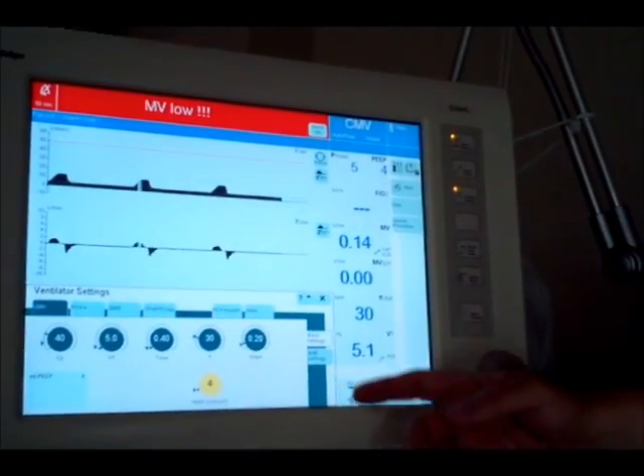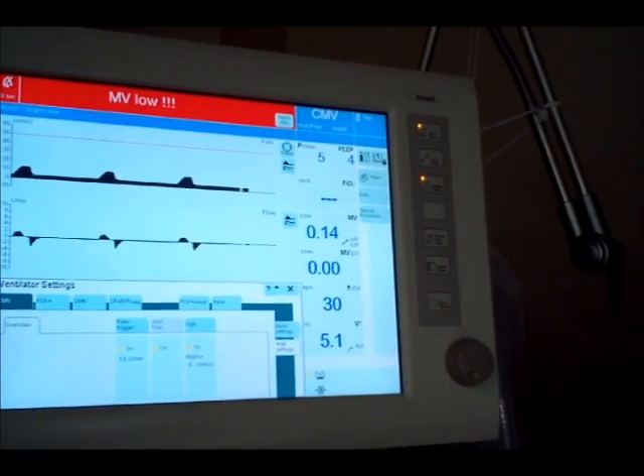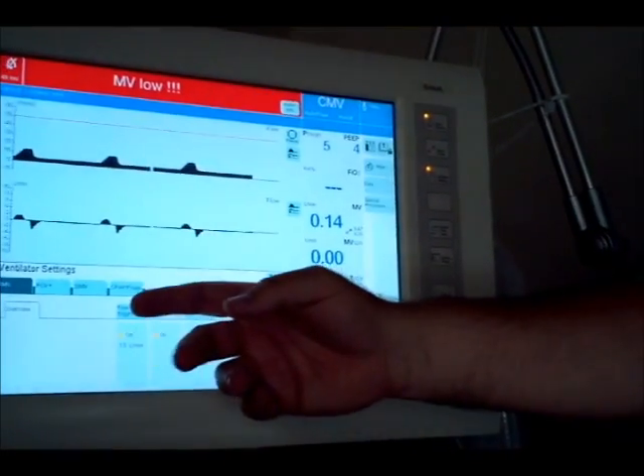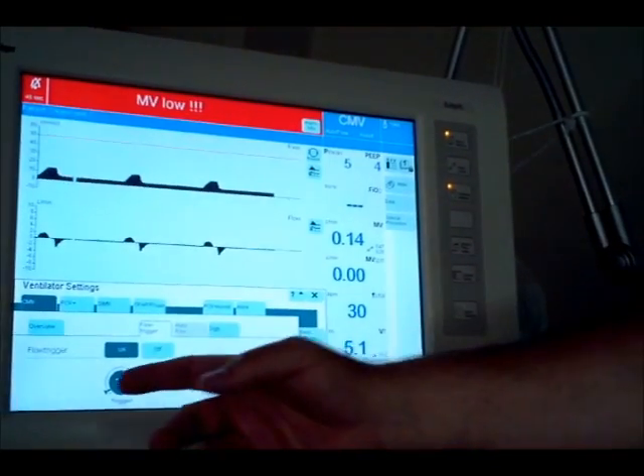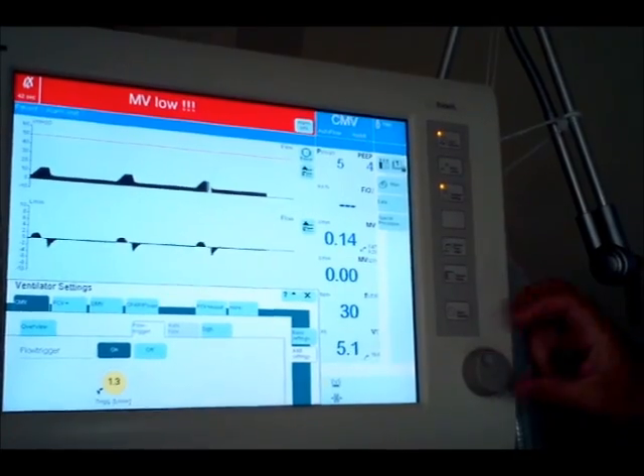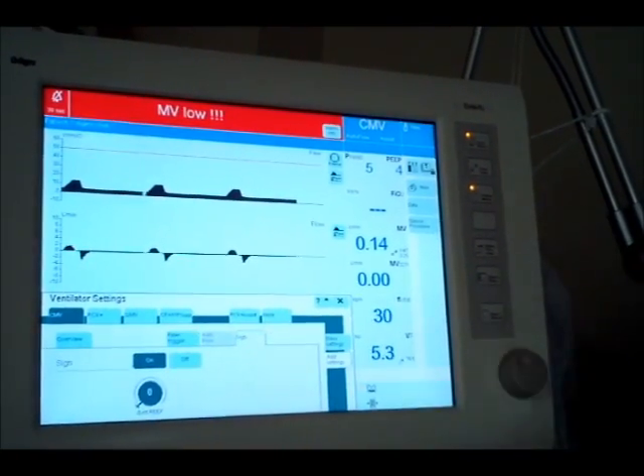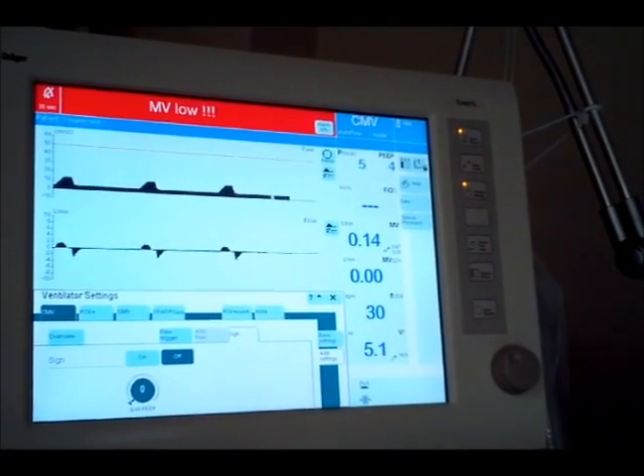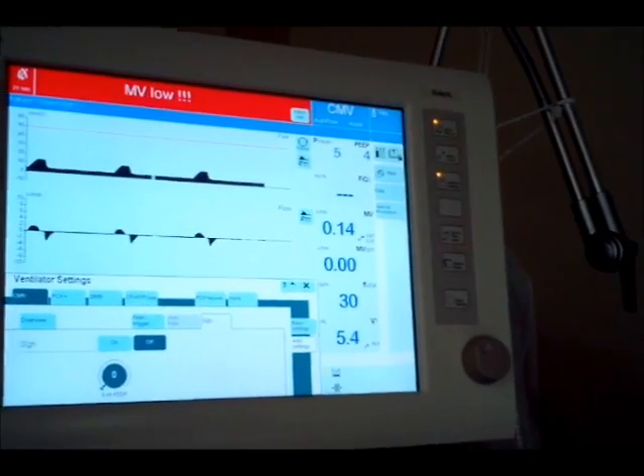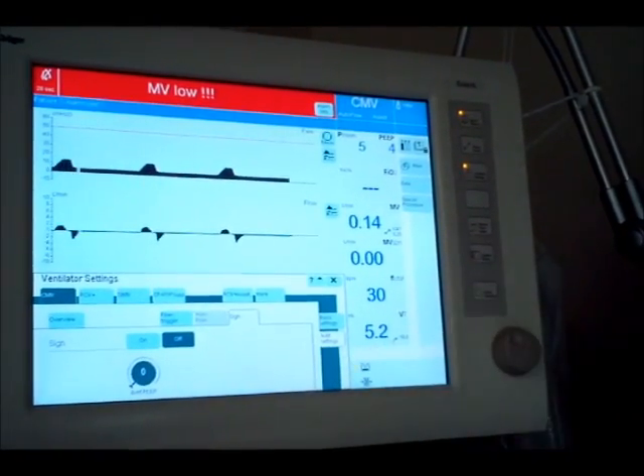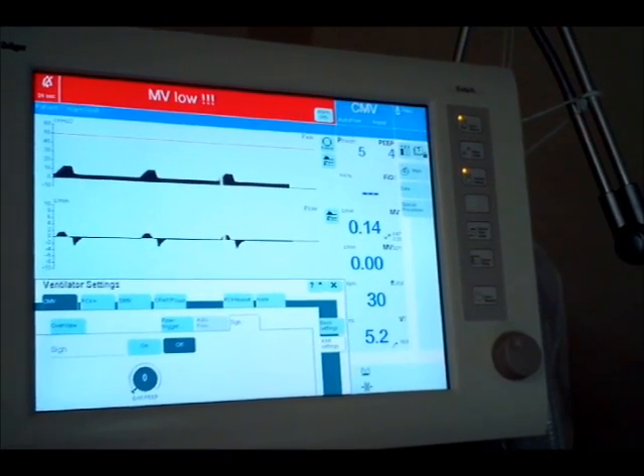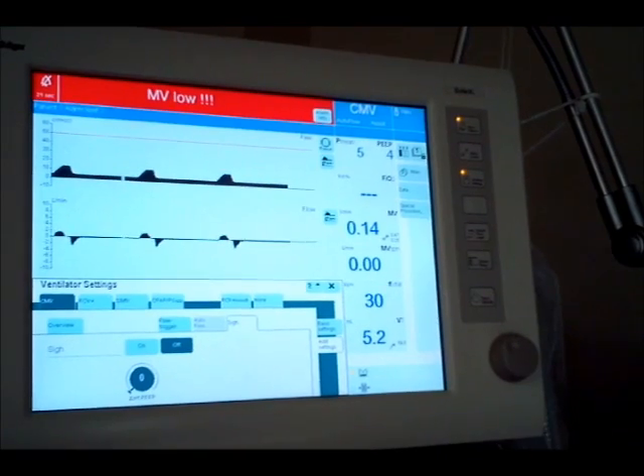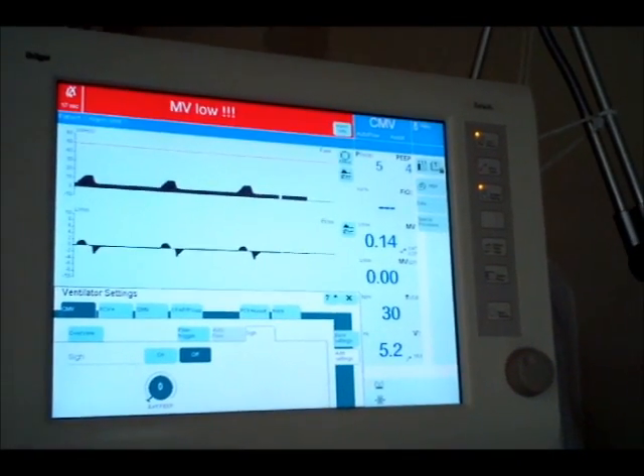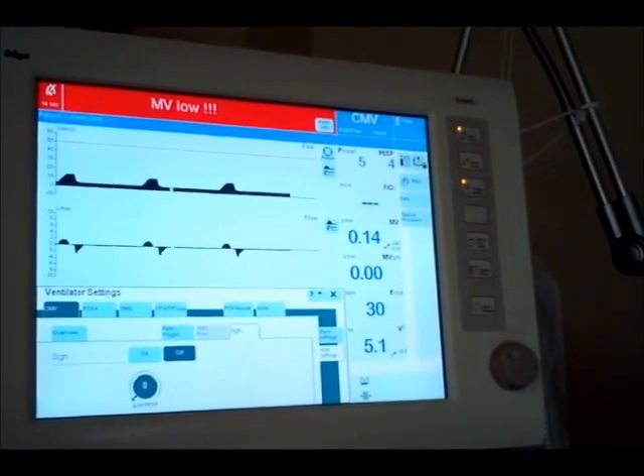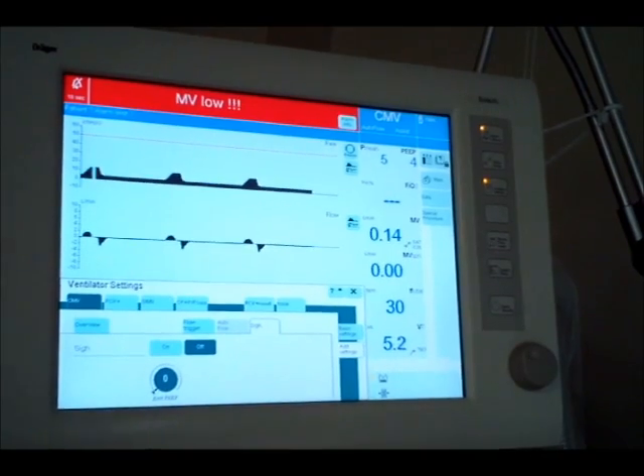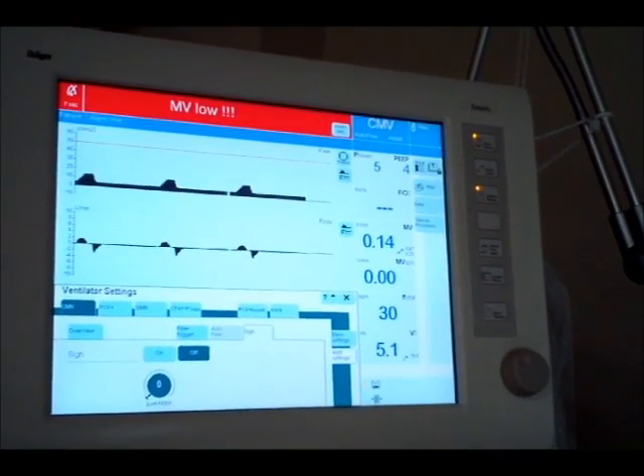If you want to, just think of, okay, I need to go into my additional settings. What's under my additional settings? What's one couple big things there. One is the flow trigger. Let's go with a 1.3 again on this one. And then the sigh, I think we'll just turn off. We'll talk about the sigh a little bit more when we do the adults. And then notice the auto flow is also available in the additional settings, but if we're using the NeoFlow, auto flow is automatically on, so we can't shut it off. Basically, what we're doing right now really is assist control with volume guarantee if we want reference to the Babylog. Because it is adjusting the pressure to try to give us that tidal volume.